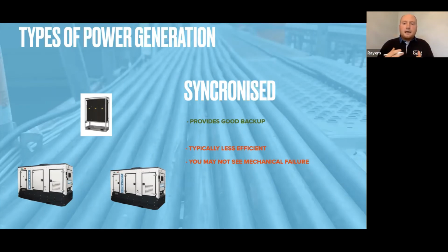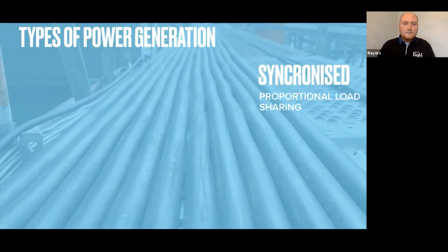So what we need to be very, very careful of, and this is something we come up against quite often with changes in riders and so on on stages, is that despite the fact we can physically deliver it, we can't back it up. And by that, I mean, if we can do 100 kVA on both machines, we need to ensure that we don't go over that, because if there's a mechanical failure, the other machine will fall over and we'll be no better off than just having a standalone generator. So those are the 3 scenarios. So you've got standalone, which is just a normal generator, AMF, and synchronized. If we could skip to the next slide, Meg, that'd be great.